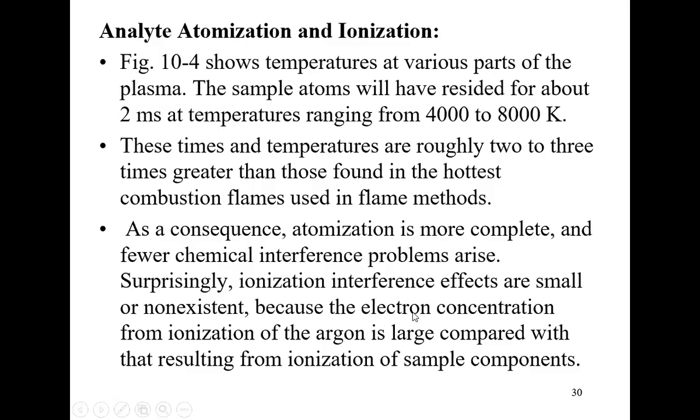This is what goes against what we know. Normally, we would think if it's a hotter temperature, you are likely to ionize it, all right? But it's very surprising that at these temperatures, 4,000 to 8,000 Kelvin, much higher than flame AA, the ionization interference effects are very small. They are nearly non-existent.